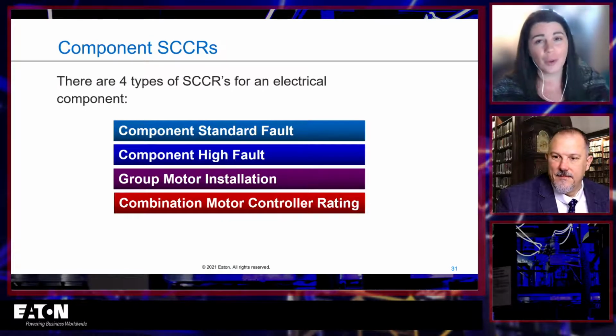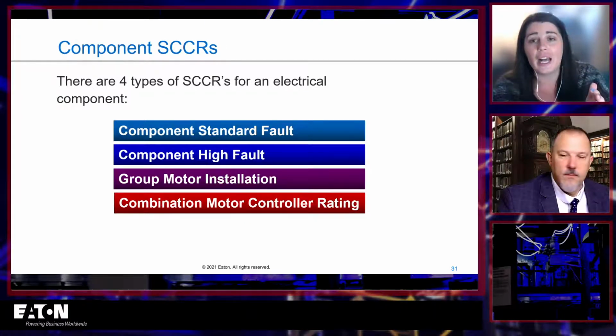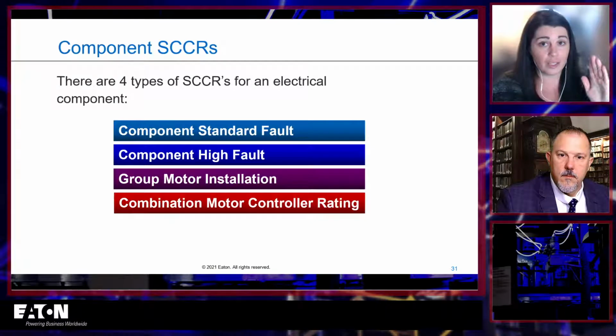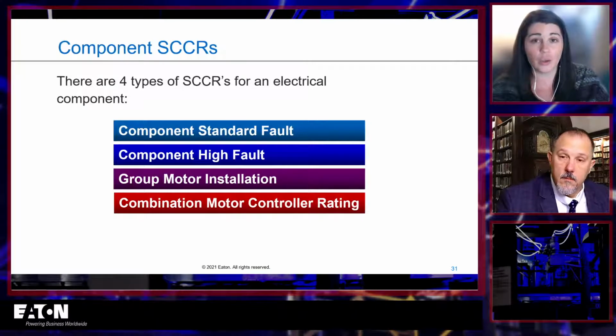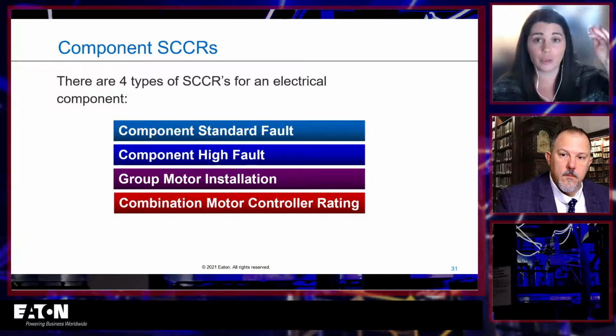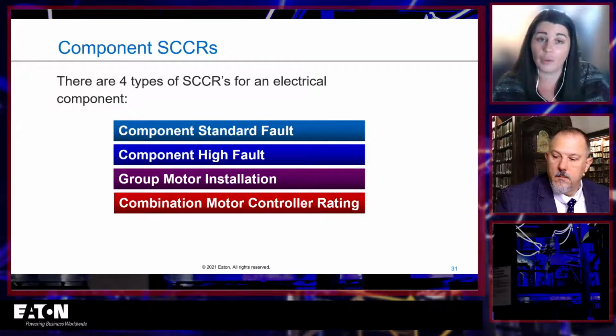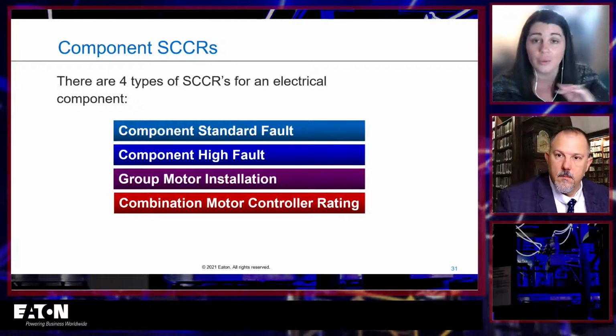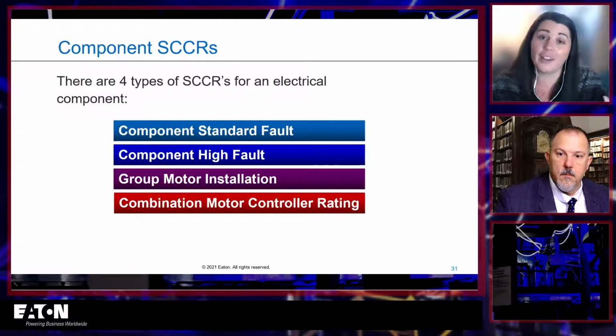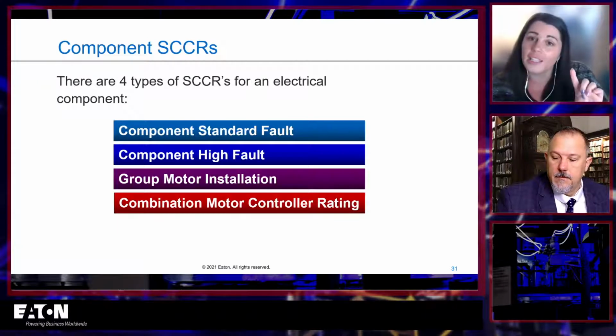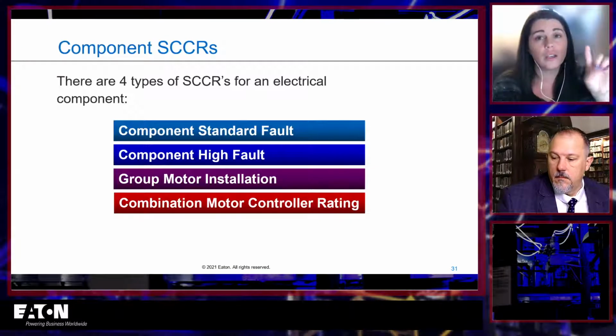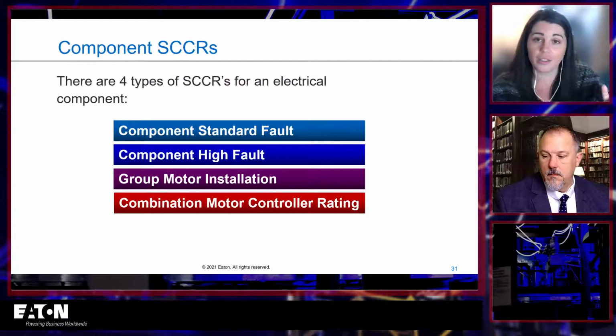The next is group motor, and group motor rating is actually very similar to high fault rating, except it's applied in a group motor application. So group motor, if you don't know what that is, is when you have one overcurrent protective device that feeds multiple controllers that each feed a motor load. The standard way to design a panel is you'll have an overcurrent protective device for every single motor controller, which goes to every load. But you can do group motor. There are reasons to do it that I won't necessarily go into, but it is a perfectly legal, acceptable way to design your panel in UL 508A, provided you follow all of the rules. But when you do it, there's a separate short circuit current rating. And that's because that upstream overcurrent protective device, right? If you have a fuse feeding 4 contactors that each go to a motor, that's obviously going to be a higher rated fuse than if it were fused to one contactor, to one motor.